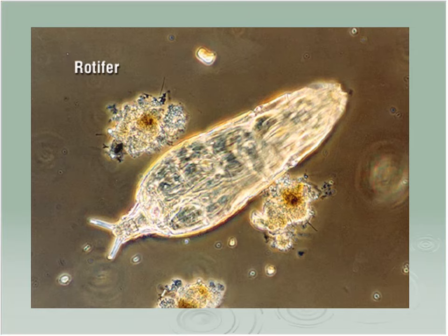As we're getting into these larger organisms, rotifer gets its name from the fact that as it goes through, it kind of spirals somewhat like a football as it moves through the water. What we're seeing, indicating when we see this type of organism in numbers under the microscope, is we're starting to get older sludge now. You see its size in relationship to this clump of millions of single-cell bacteria all clumped up.